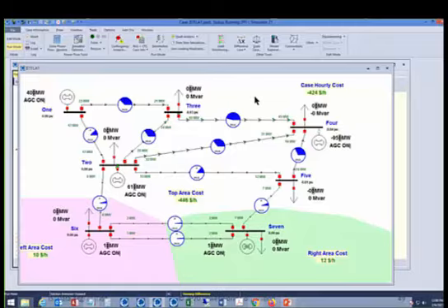And now what I'm seeing is the differences between the two cases. So this 45 megawatts of flow that shows up on this line from 3 to 4 means there's 45 more megawatts flowing with this generator out of service than there was before. And the generator itself has a negative 95 because in the base case it was doing 95. Now it's doing 0.